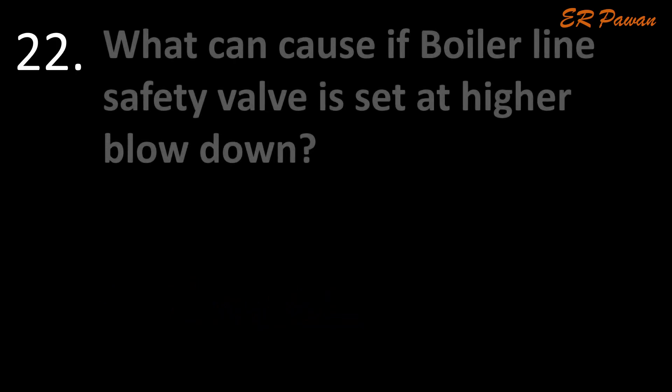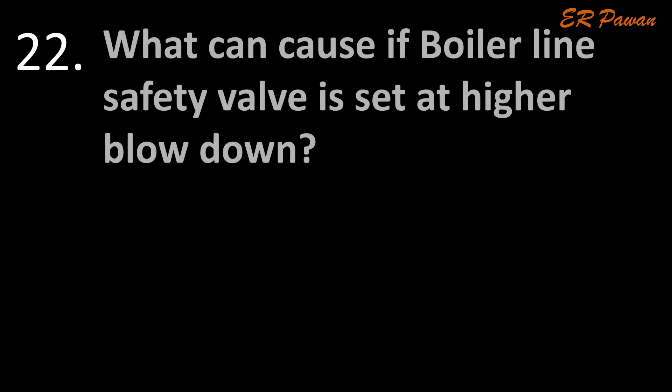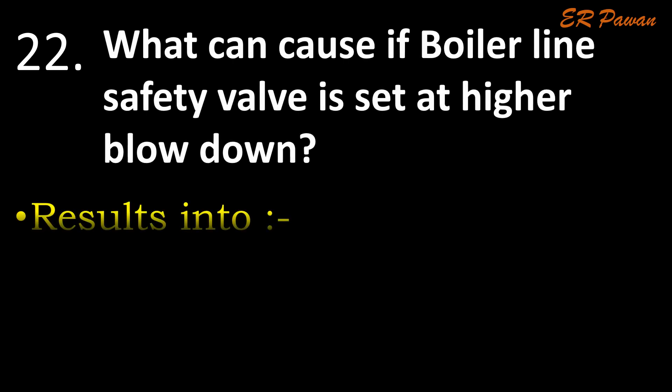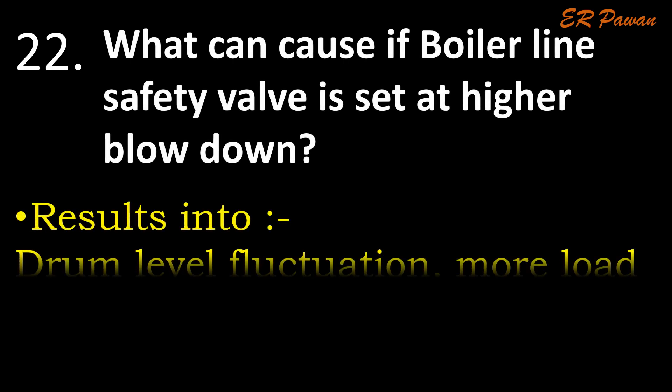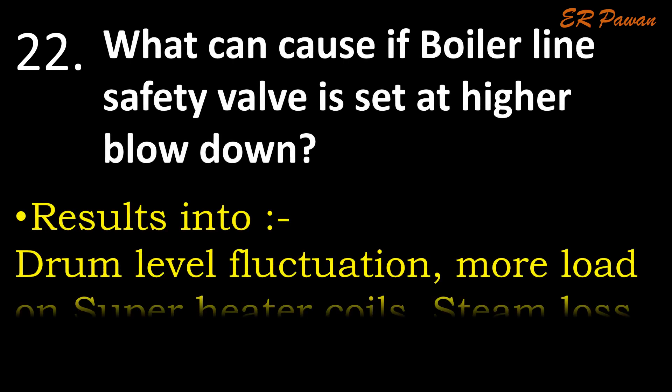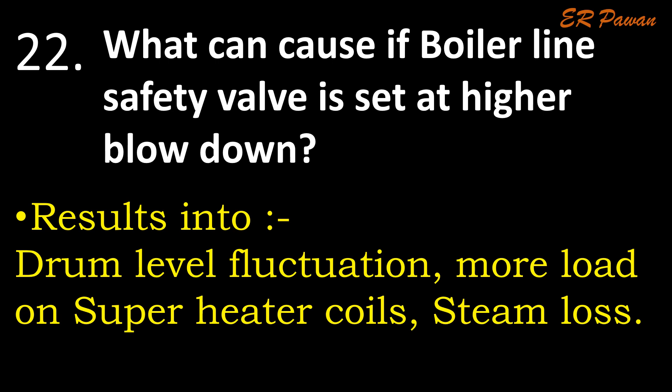Question 22: What can happen if a boiler line safety valve is set at higher blowdown? It results in drum level fluctuation, more load on super heater coils, and steam loss.